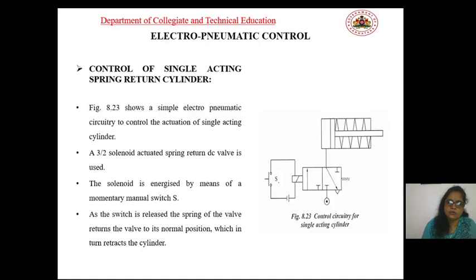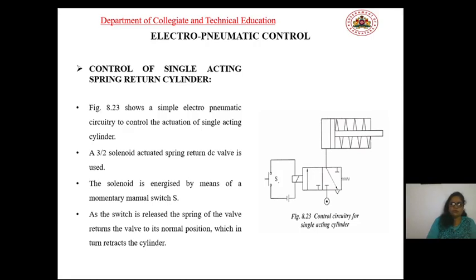Electro-pneumatic control: here we discuss the control of a single-acting spring-return cylinder. The figure shows the control circuitry for a single-acting cylinder. The electro-pneumatic circuitry to control the actuation of a single-acting cylinder utilizes a 3/2 solenoid-actuated spring-return DC valve.